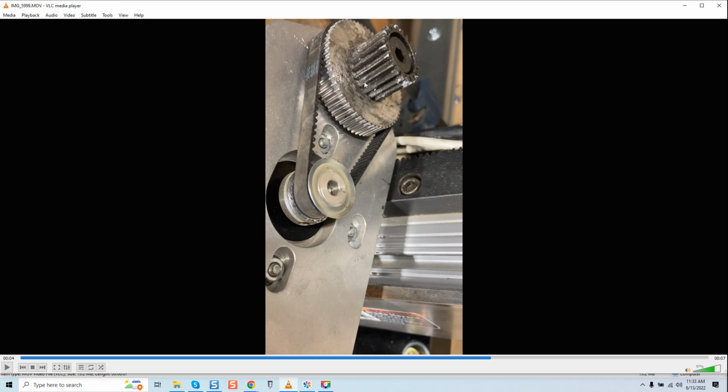But a couple hours going over this machine, cleaning everything, going through the process of what I just said to isolate this axis, you'll certainly find it. Again, isolating a drive from a motor, very simple to do. Once again, we change the accessories connected to the drive. First, we validate the drive is good by changing the motor itself with another motor from another verified axis that's working. 99.9% of you will always have a motor available from a previous axis that is working fine, and then you're good. And that's the whole key, is going through and learning that process. Document it, document it, document it. Become scientific and precise.